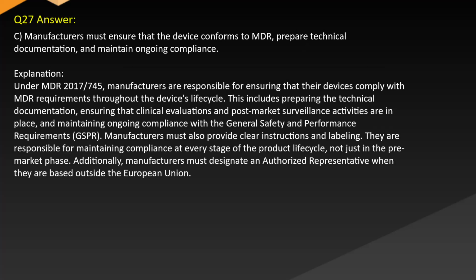Answer. C. Manufacturers must ensure that the device conforms to MDR, prepare technical documentation, and maintain ongoing compliance. Explanation. Under MDR 2017-745, manufacturers are responsible for ensuring that their devices comply with MDR requirements throughout the device's lifecycle. This includes preparing the technical documentation, ensuring that clinical evaluations, post-market surveillance activities are in place, and maintaining ongoing compliance with the General Safety and Performance Requirements (GSPR).